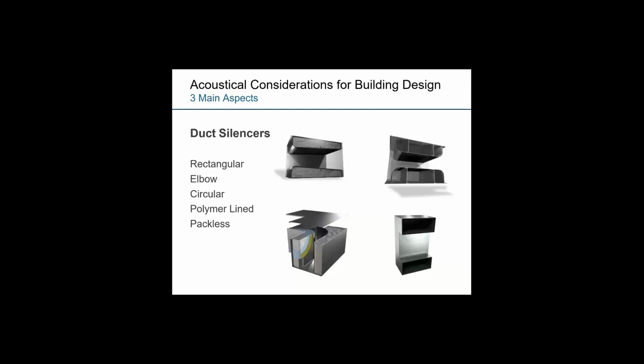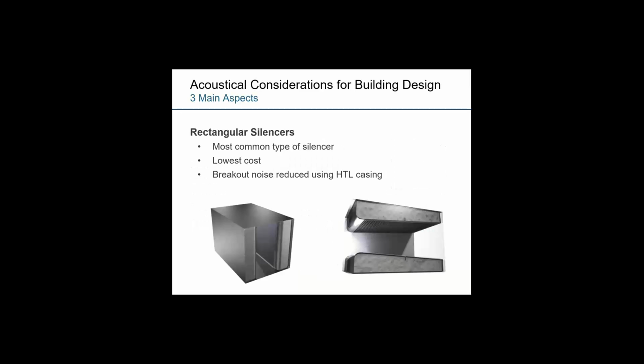Silencers in general look something like these here, where there's a variety of different types and styles, and they're primarily used for attenuating ducted noise. It doesn't always have to be ducted. Sometimes they're used in unducted applications, but primarily a duct silencer is installed into an HVAC system to attenuate that supply or return sound energy. Rectangular silencers typically look something like this here, where there's an outer casing and then internal baffles that are primarily used for absorbing and attenuating that sound energy present.